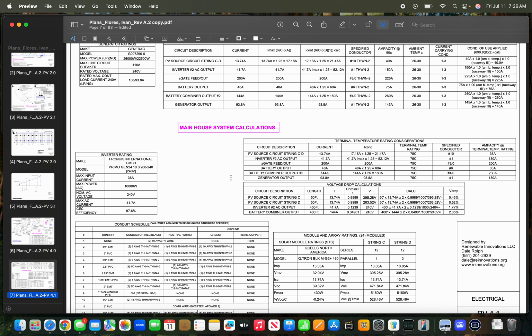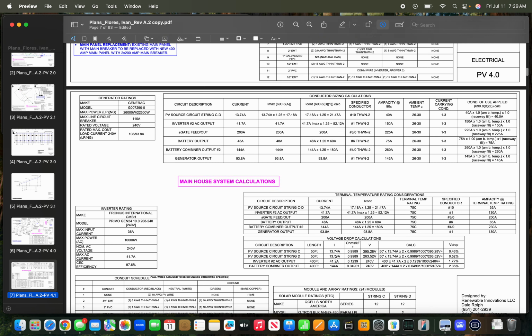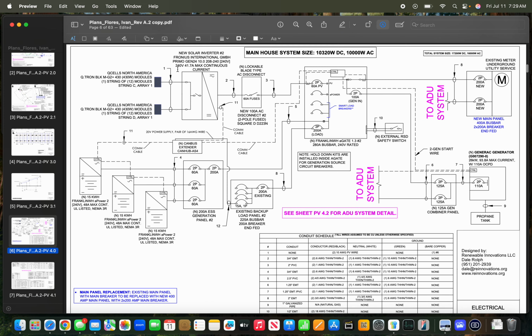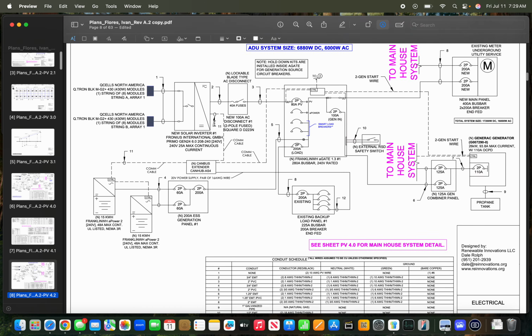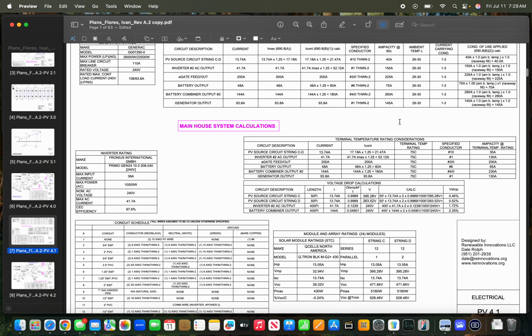We don't need to get into all of this, but we had to check the array configuration for the strings. That's what I was looking at over here. For this, we don't want to exceed the 600 volt maximum input on this inverter, which we don't, based upon the temperature for the region. This also has all our wire and voltage drops and everything in there, what we should be looking at in terms of current. So this is all good information to review, and most of you may not understand it, and that's why it's good to just consult with someone that does and is familiar with these things.